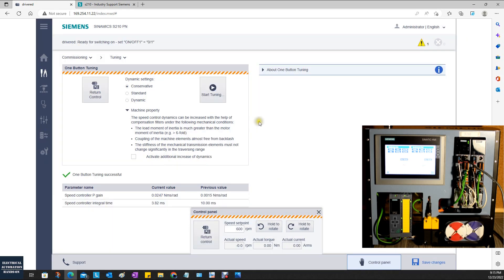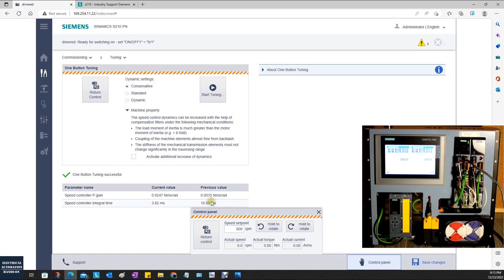This tuning finished very quickly. It definitely runs just within two revolutions back and forth. In the meantime, we see because we selected conservative, this current gain P-gain is 0.02, and the speed integral is 3.8 here.